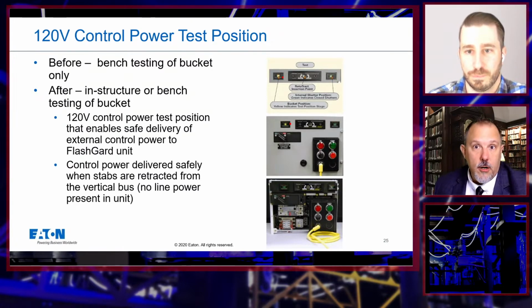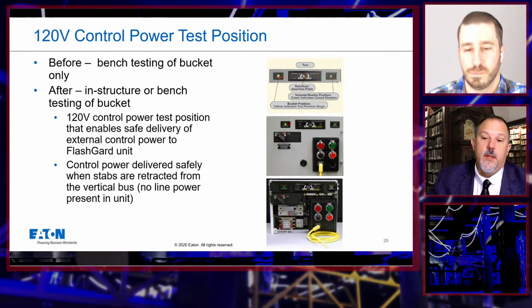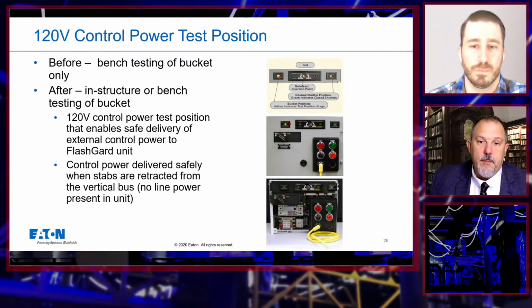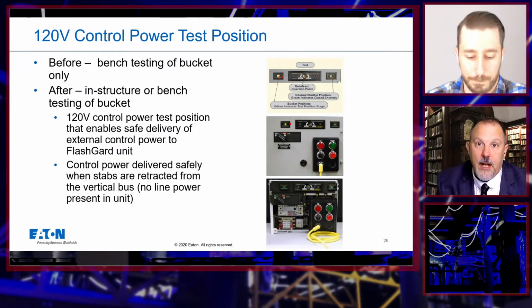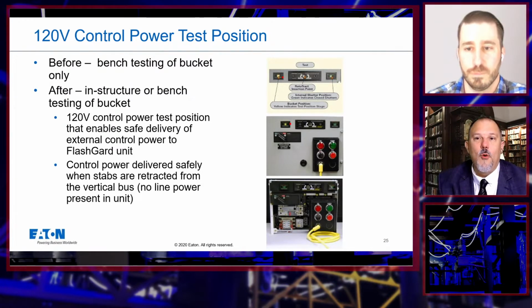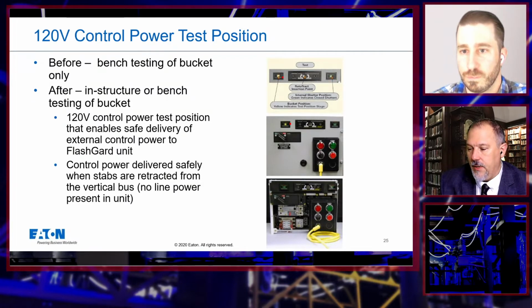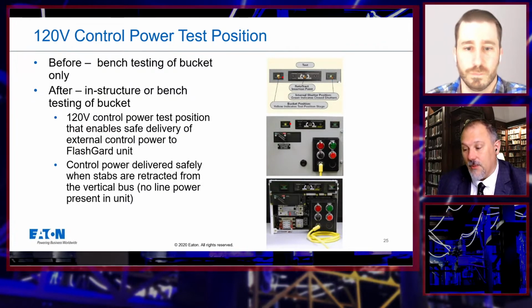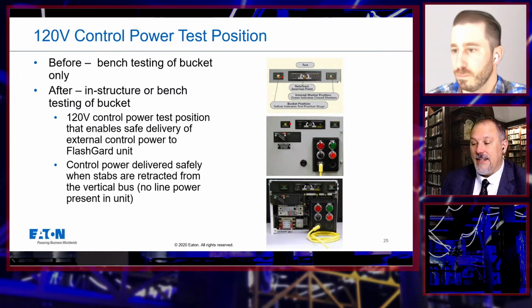For example, the arc quencher: there are certain procedures, and we have equipment that will put light sources at various locations within the equipment. It will generate a small amount of current, but it won't fire off the arc quencher, that blue box that you have to replace. But it'll test all the different components to make sure they're all functioning correctly. So, Tamaki, you're accurate that it does not directly relate to the arc resistant equipment session.